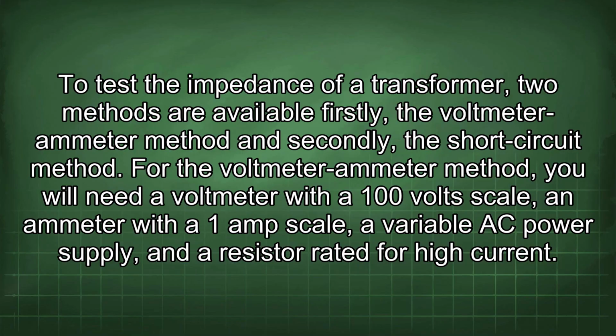To test the impedance of a transformer, two methods are available. Firstly, the voltmeter-ammeter method, and secondly, the short-circuit method. For the voltmeter-ammeter method, you will need a voltmeter with a 100-volt scale, an ammeter with a 1-amp scale, a variable AC power supply, and a resistor rated for high current.